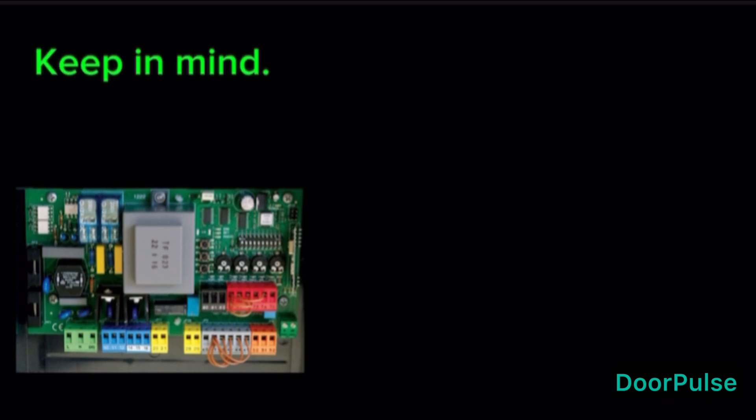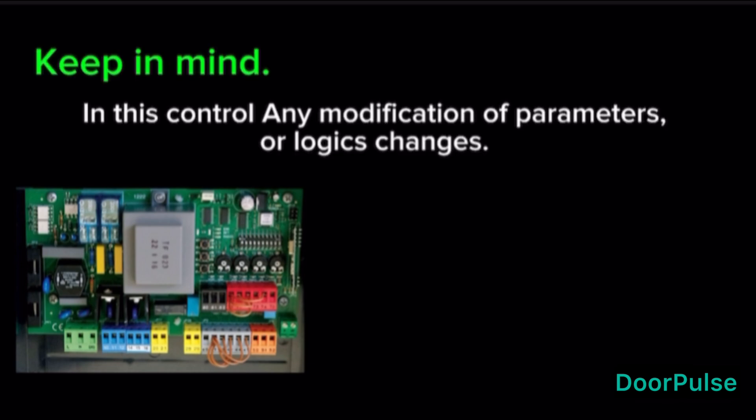Keep in mind, in this control any modification of parameters or logic changes must be confirmed by pressing S2 button 5 seconds. When any change coming S2, LED will light up. By pressing 5 seconds, light will go out.